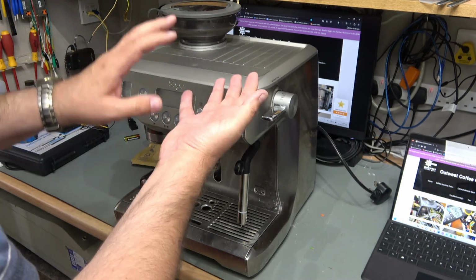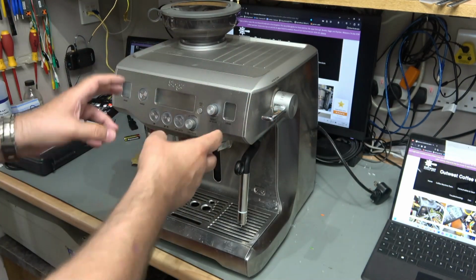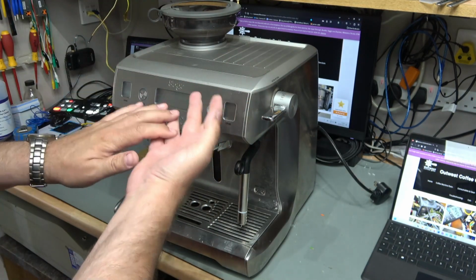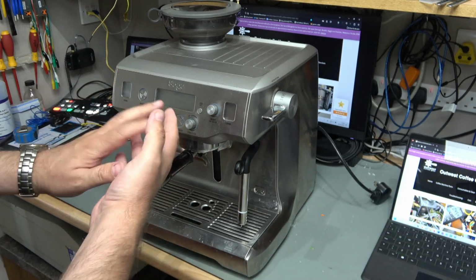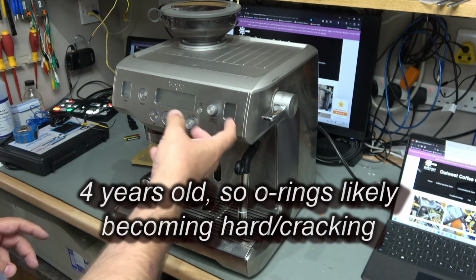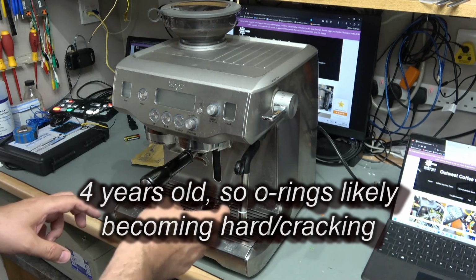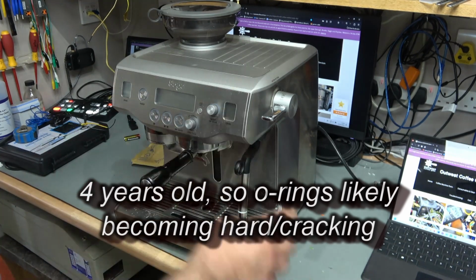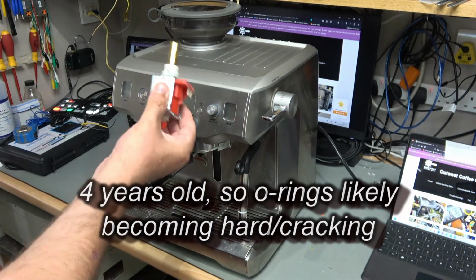So the plan is to take it apart, take out the water level sensors, clean those, put them back in, take everything out of the boiler essentially, replace all the O-rings, and also possibly, I'm less sure about this, possibly replace this.